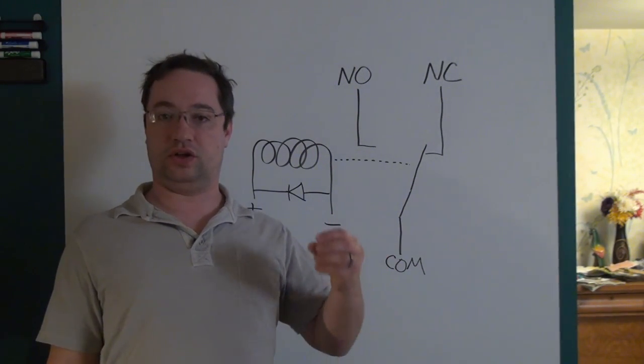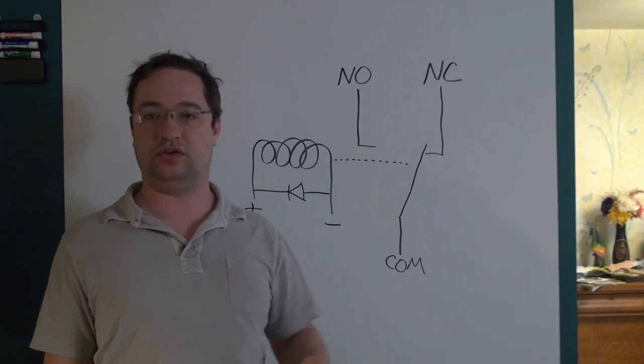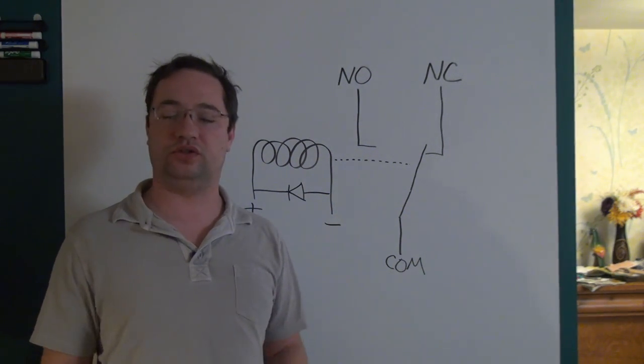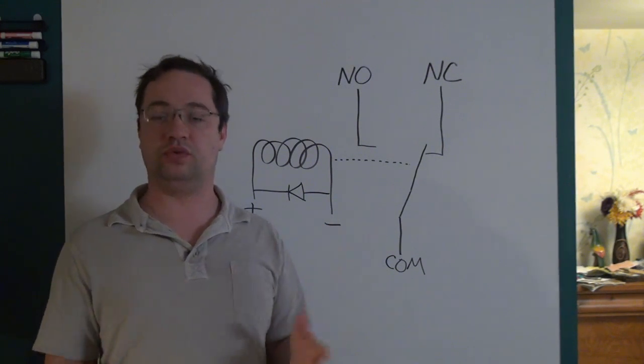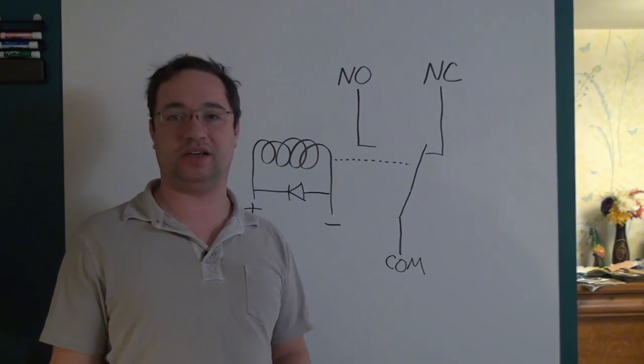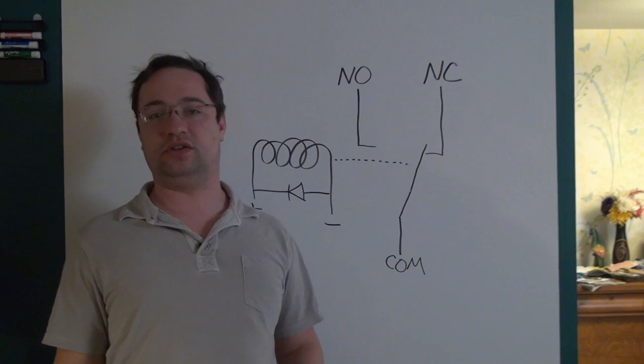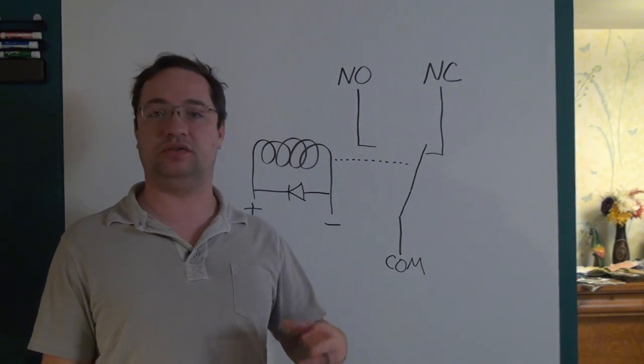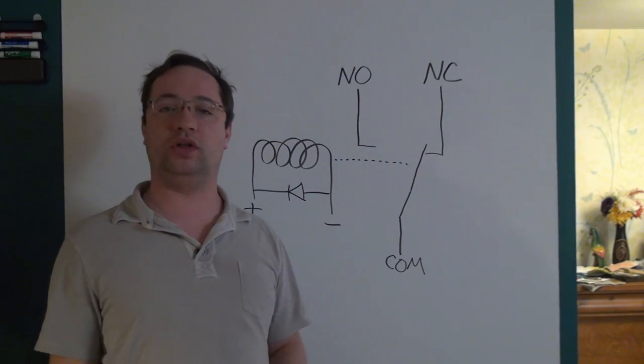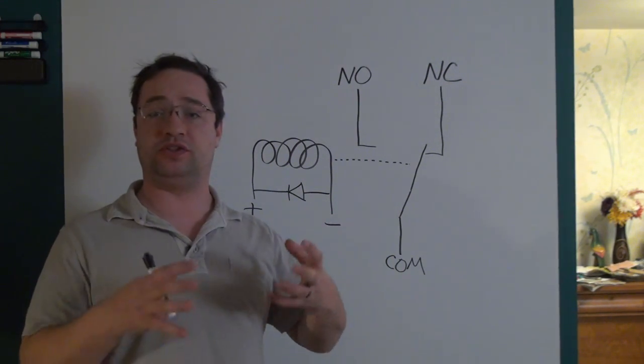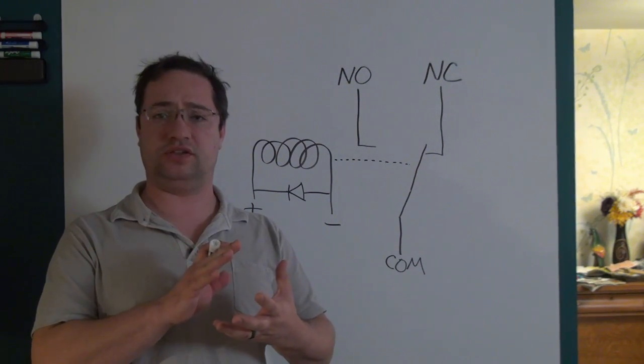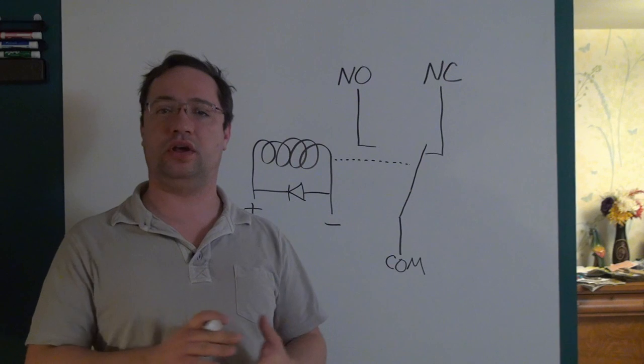As relays get a little bit larger, in the range of 1 amp to 10 amps, you're in the normal relay range. When you get to the really big relays, they're generally referred to as contactors — we're talking up to thousands of volts and hundreds if not thousands of amps. Those relays can be quite large and are specifically designed to break large currents, with contacts that have special designs to minimize arcing.